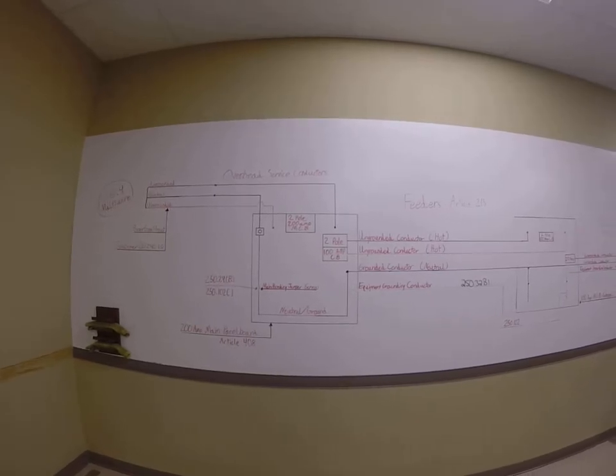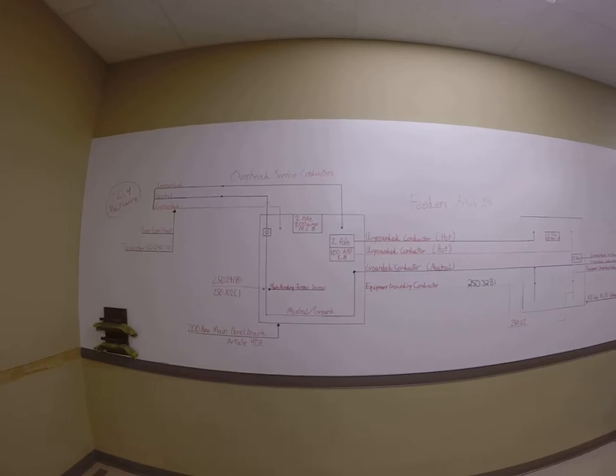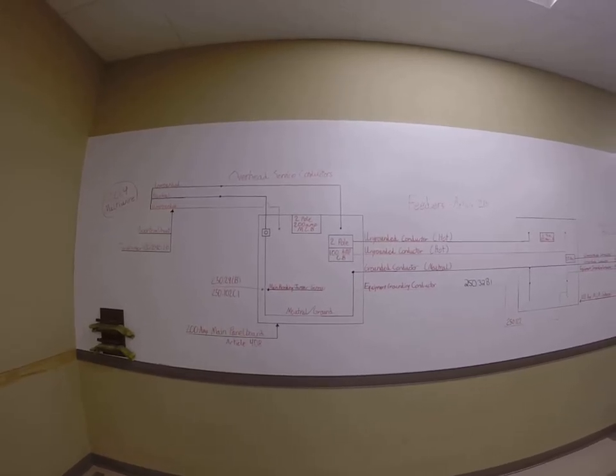Now, this piece represents, let's just say hypothetically, you have a 200 amp main panel. And in that 200 amp main panel, I've got a bunch of circuit breakers that I didn't draw in, but I've got another breaker that's a 2-pole 100 amp. Let's just say that's the one on the right. And somebody says, I want a sub panel to be put somewhere else. I don't care. It could be anywhere. It could be a detached garage or something like that. And you ran 100 amp cable over to that panel. However you got it there is irrelevant.